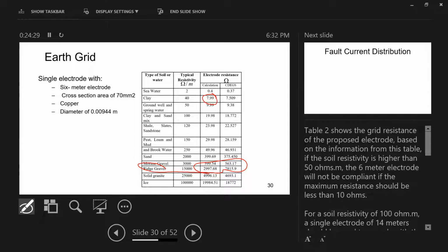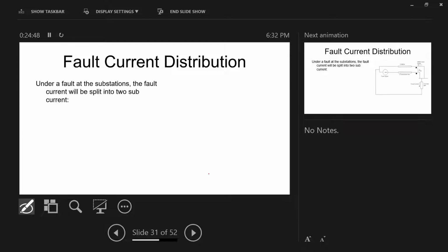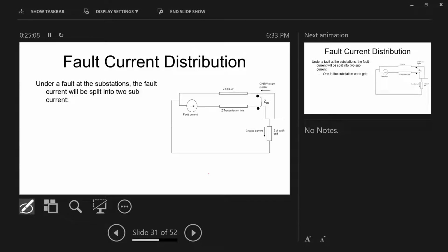Under the standard, we are not allowed to commission a substation without having a resistance of less than 1 ohm. You must imagine you have to drive this from 3,000 ohm down to less than 1 ohm for you to be allowed to commission a substation. Because in the substation you have the voltage, the current is very high, the fault current. So when you have very, very high soil resistivity in the substation, we can use our transmission line, so-called overhead earth wire. And nowadays, by the way, it's a communication line. It's called optical fiber ground wire.